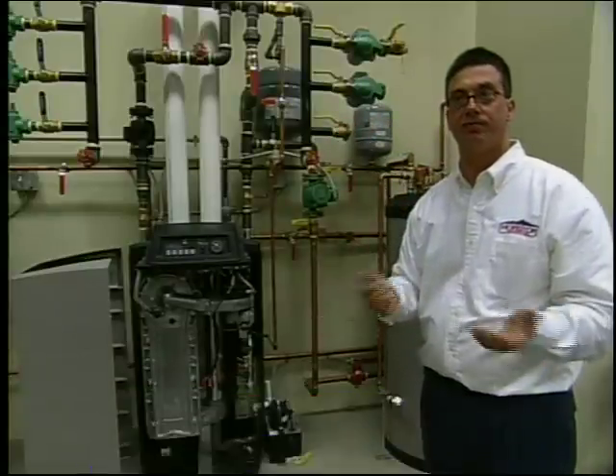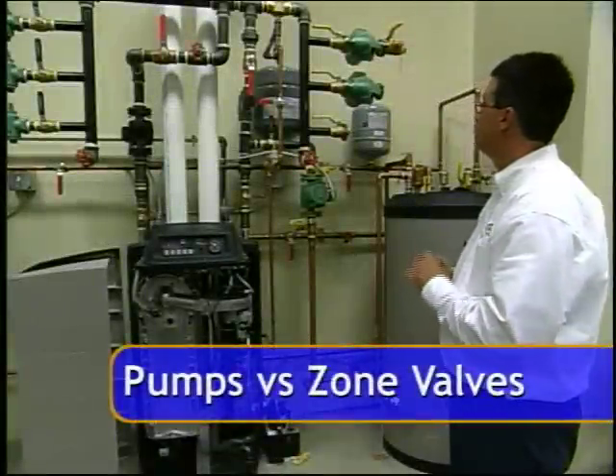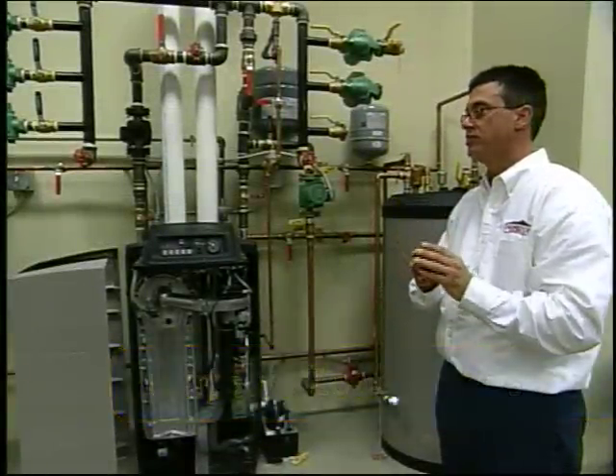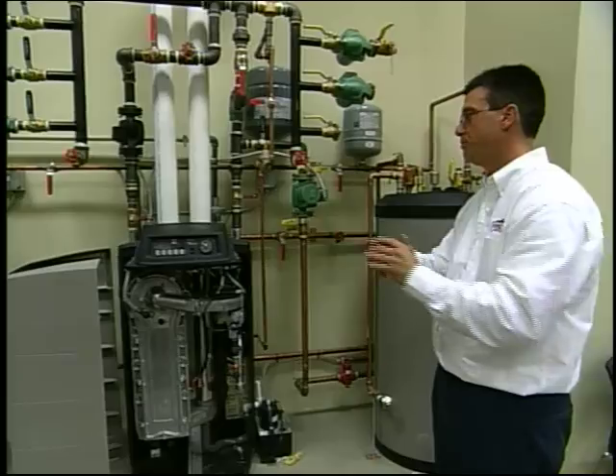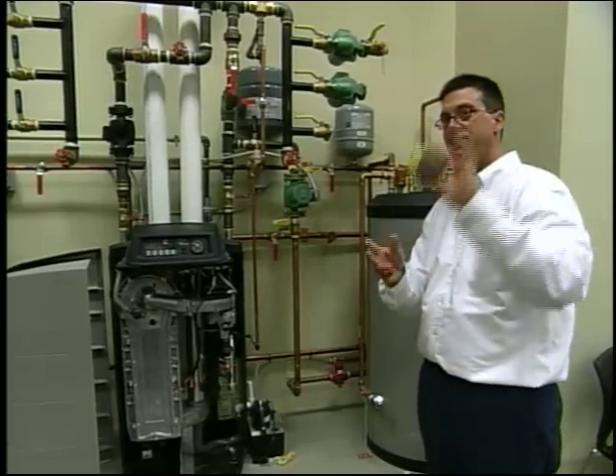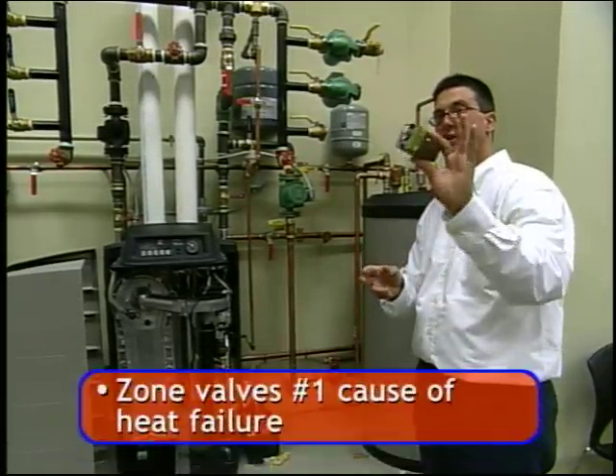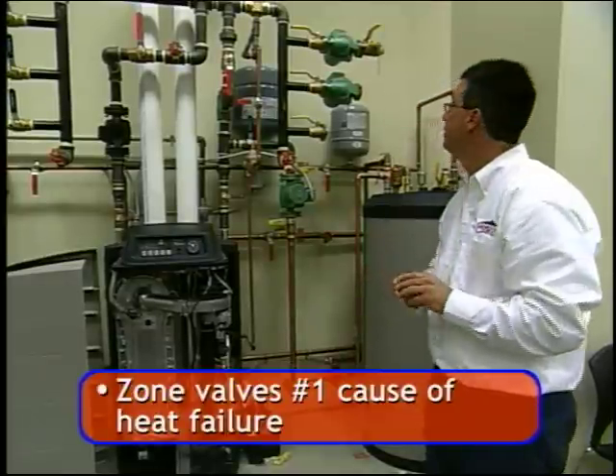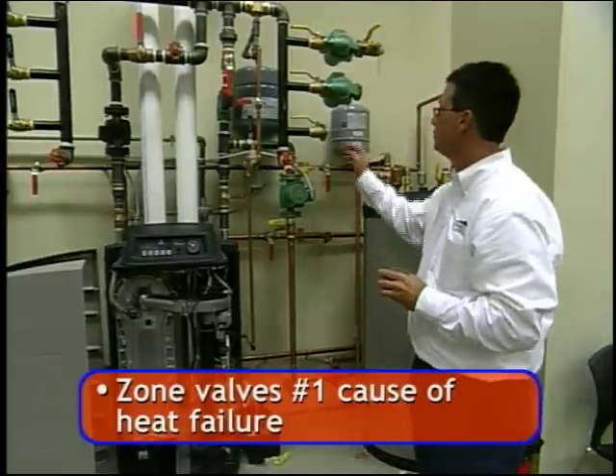Why we use pumps and not zone valves? You've seen zone valves. Zone valves are existing. As a matter of fact, when most people replace boilers, they leave the existing zone valves, when in fact the zone valves are the #1 cause of hydronic failure. We use pumps. We use pumps for each zone.